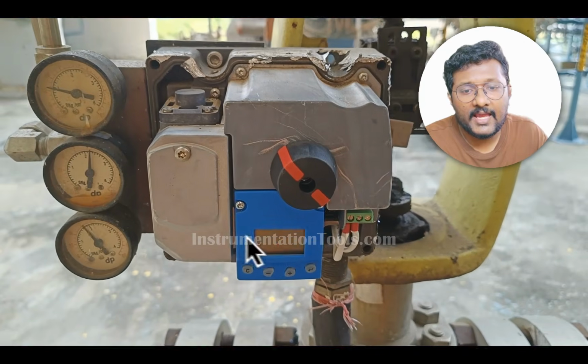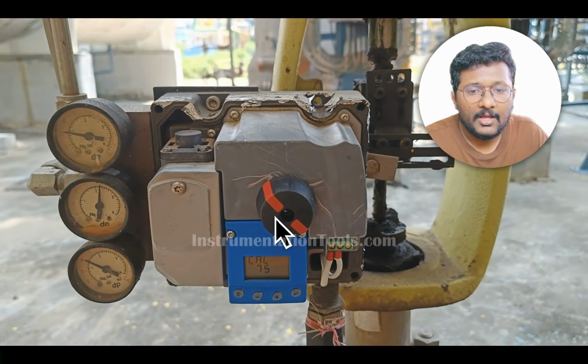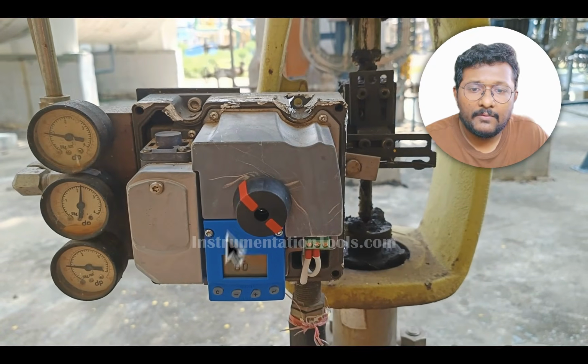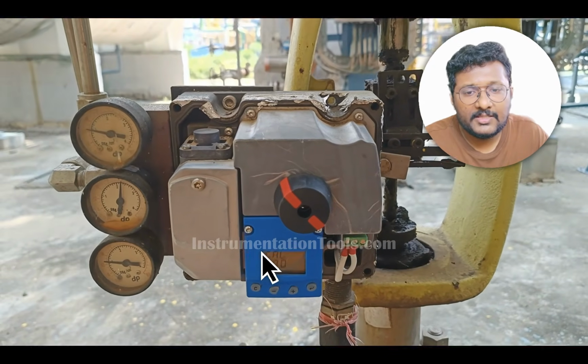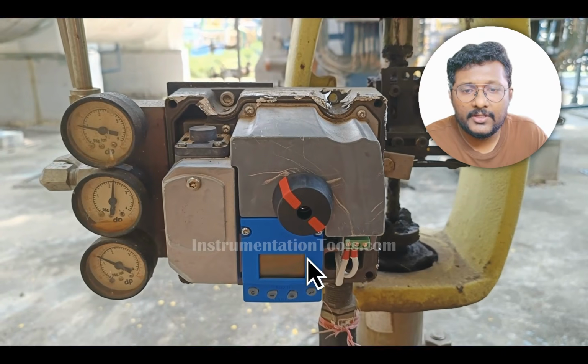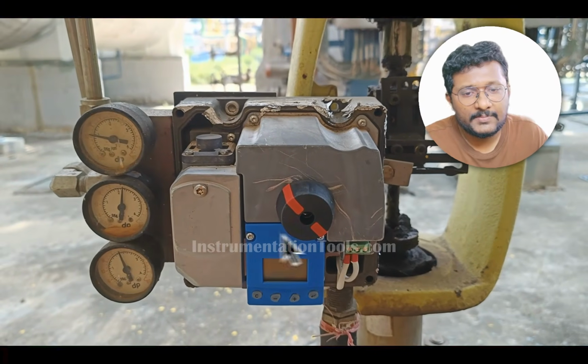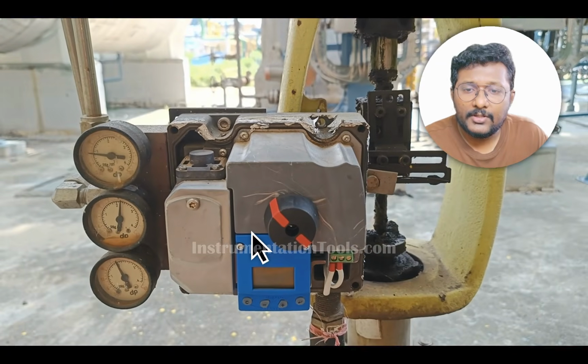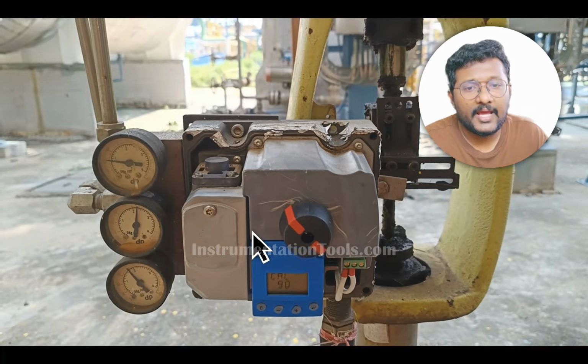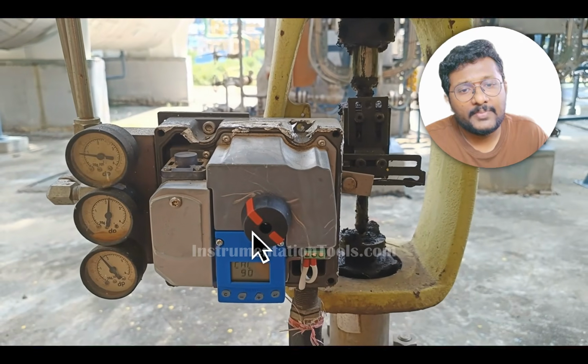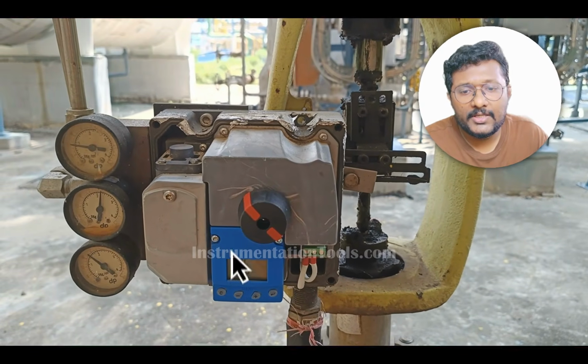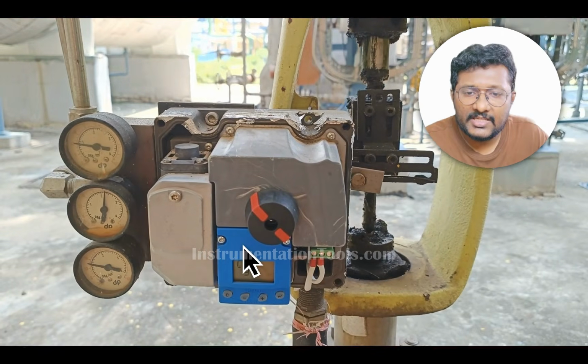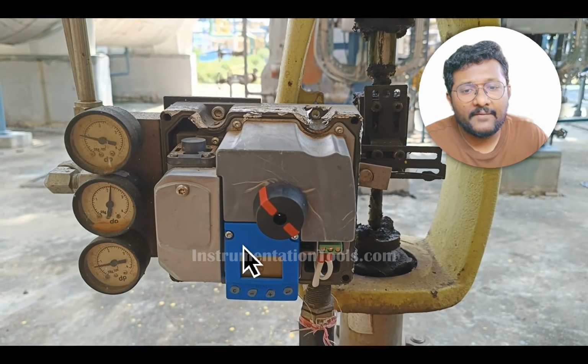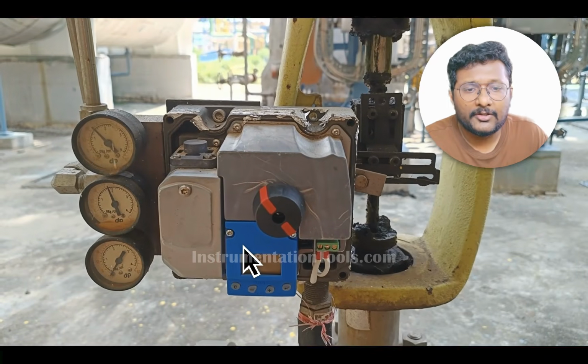Now the status is cal 75. Remember, when you have a valve positioner display, it is the recommended method to do the calibration from this display, because your HART communicator may take some time. For a maintenance plant, we usually use the available display. If there is no display available, then only we use HART communicator.